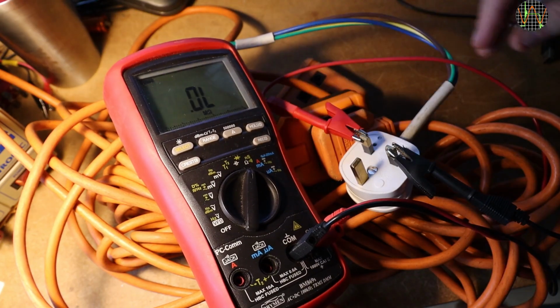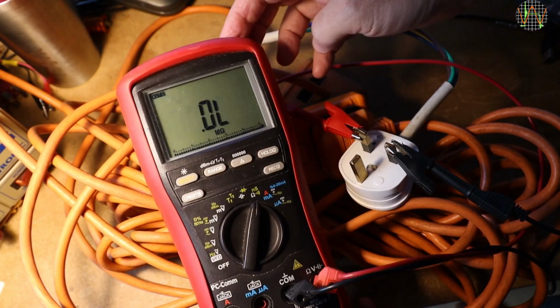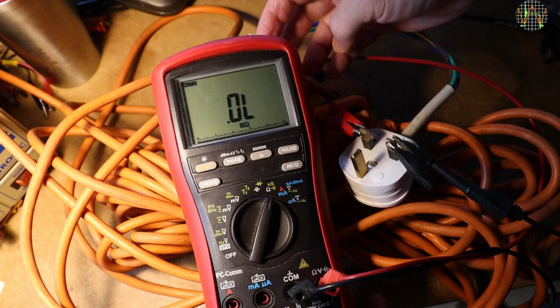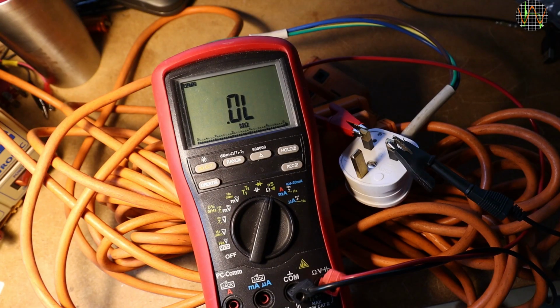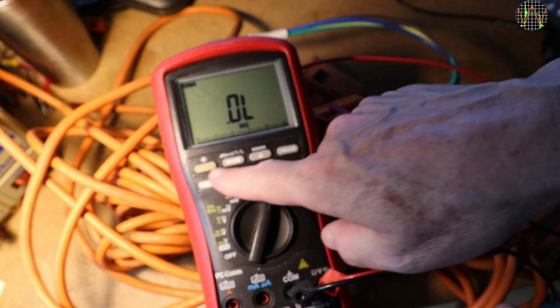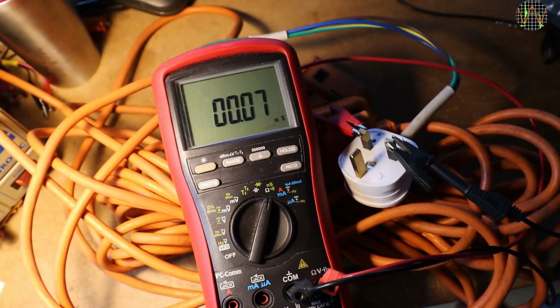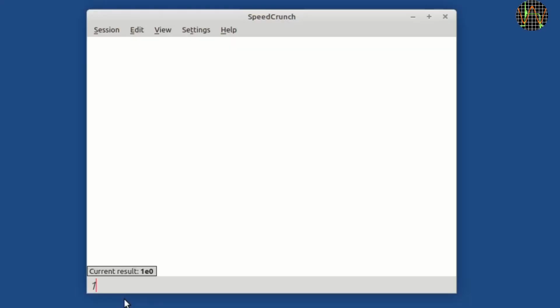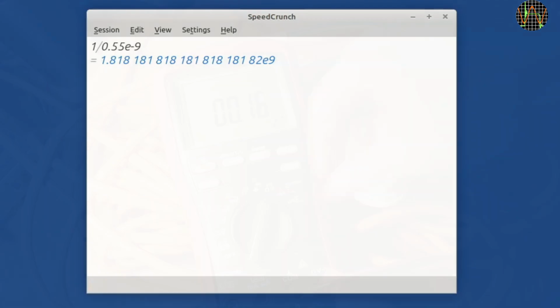Measuring the resistance between L and N, as you expect, it's higher than what the resistance mode can measure. But for such cases, some meters, including this one, have a conductance mode. Letting it settle for a while, it shows a conductance of 0.55 nanosiemens. To convert nanosiemens into ohms, you need to take the reciprocal, so 1 over 0.55, and nano means 10 to the power of minus 9. The result is 1.8 gigaohms. Clearly this is not the cause of the leak.